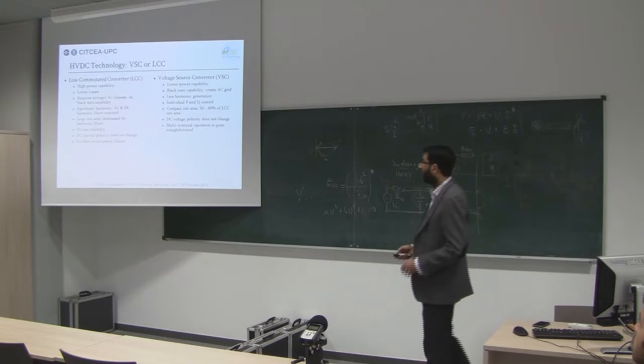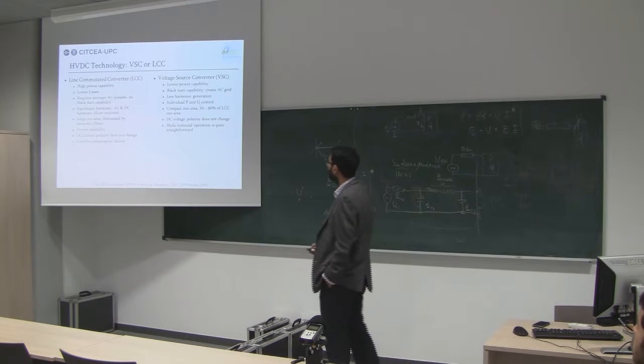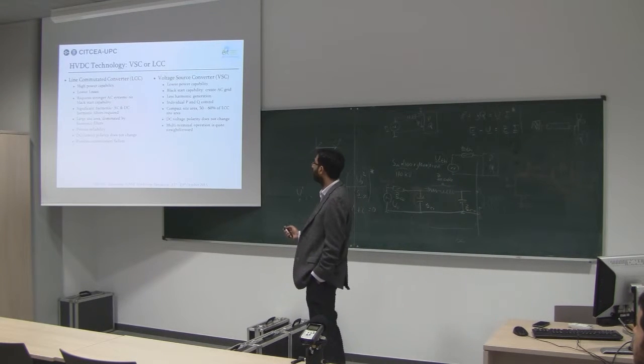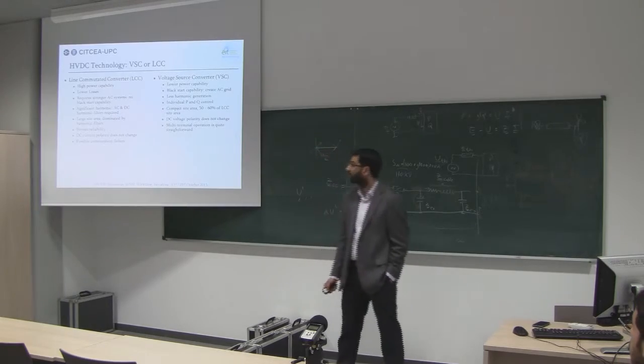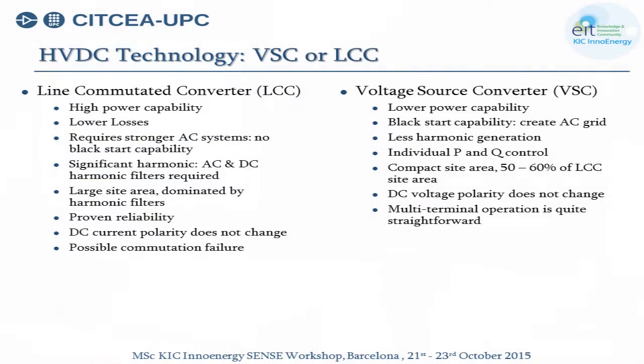For this offshore grid, we need to use a voltage source converter as compared to a line commutated converter. The main difference is that the voltage source inverter has the ability to create a grid, like a black start, because offshore we cannot establish the grid ourselves.